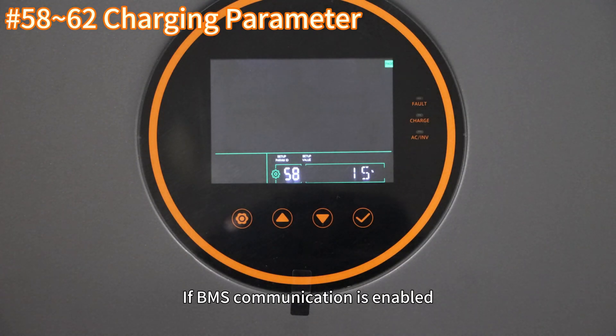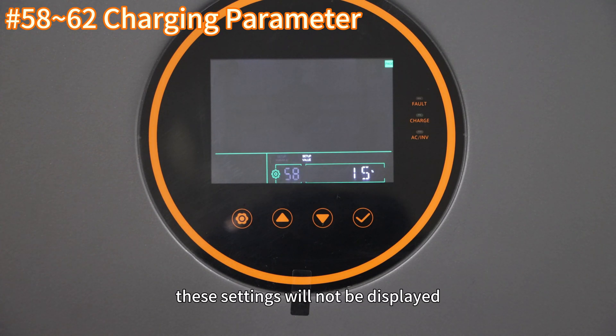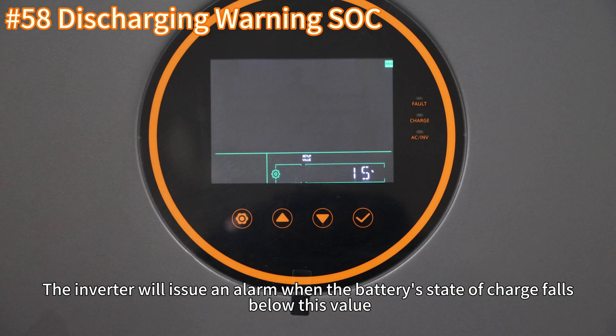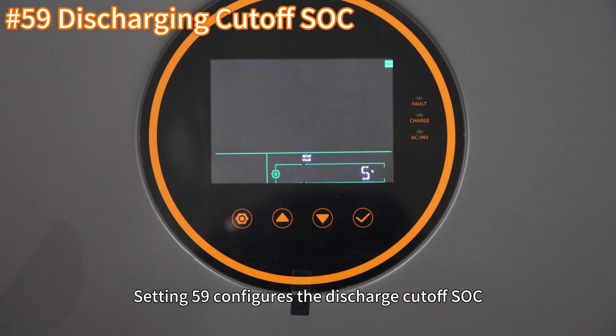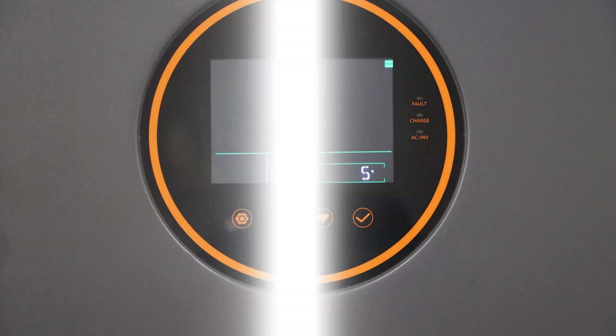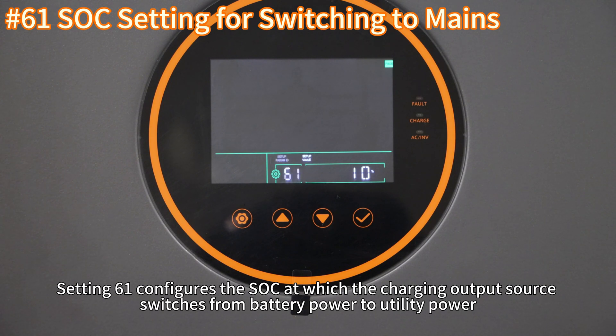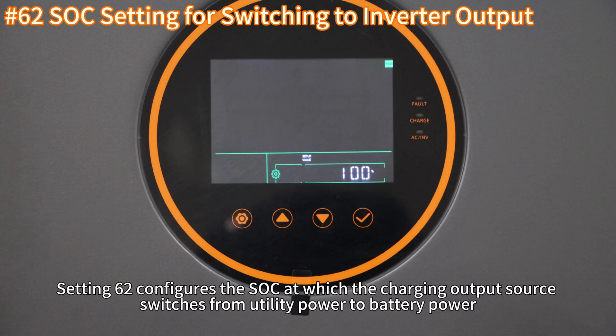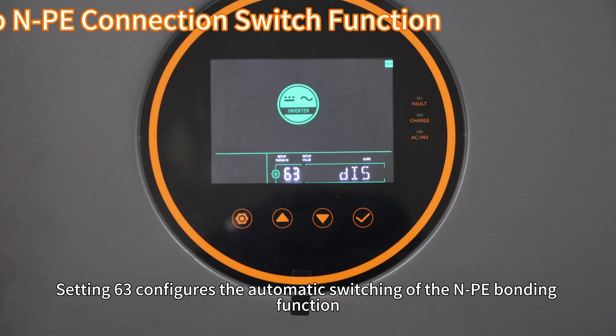If BMS communication is enabled, settings 58 to 62 can be customized; if BMS communication is not selected, these settings will not be displayed. Setting 58 configures the discharge warning SOC — the inverter will issue an alarm when the battery state of charge falls below this value. Setting 59 configures the discharge cutoff SOC — the inverter will stop battery discharge when the SOC falls below this value. Setting 60 configures the charge cutoff SOC — the inverter will stop charging when the battery's SOC reaches this value. Setting 61 configures the SOC at which the output source switches from battery power to utility power. Setting 62 configures the SOC at which the output source switches from utility power to battery power. Setting 63 configures the automatic switching of the N-PE bonding function.